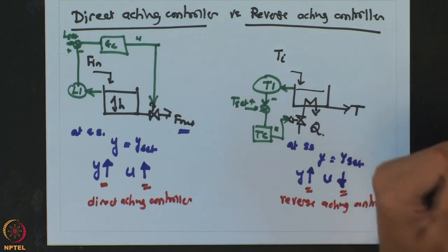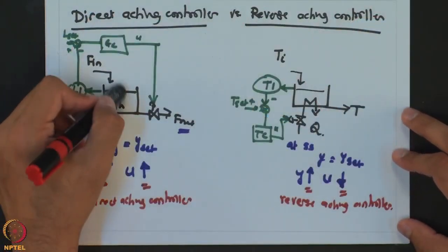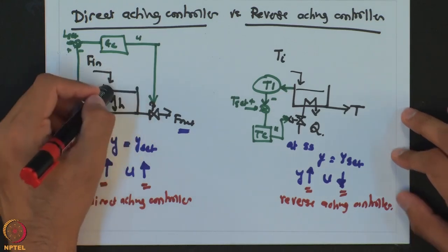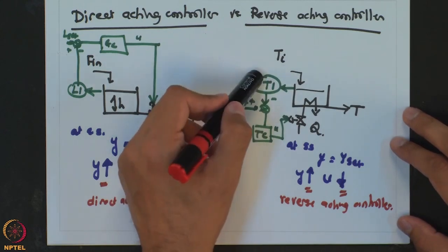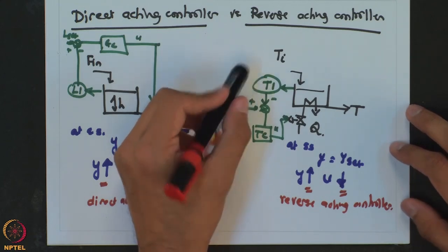It is very essential that you know the type of action of the feedback controller — whether it is direct acting or reverse acting. If you use a reverse acting controller to control the level process, the level will never be maintained. Similarly, if you use a direct acting controller for the stirred tank heater, the feedback system will never maintain the temperature at its desired value. This determination is not straightforward in industrial implementations because the same system may give direct or reverse action depending on the type of actuator inside the process.